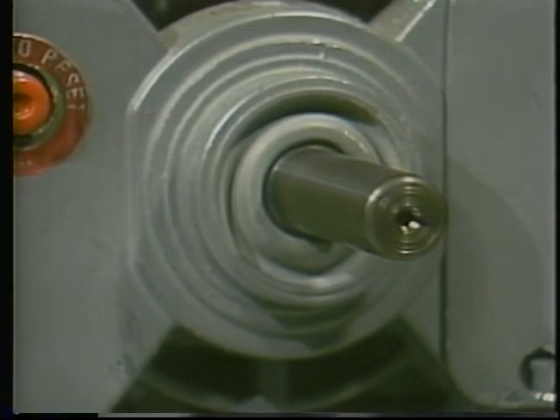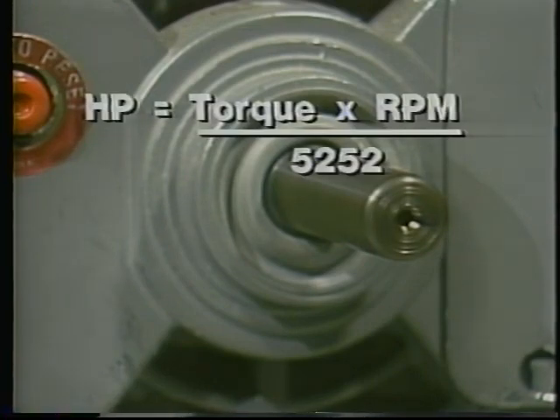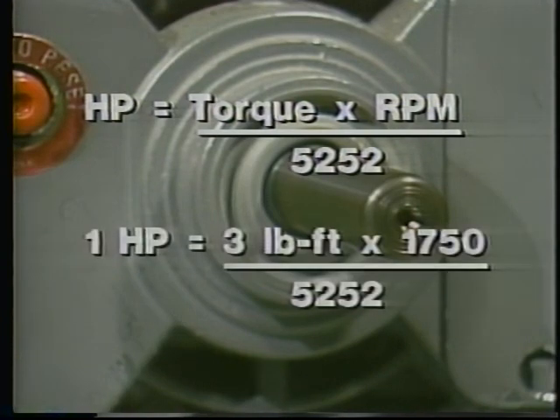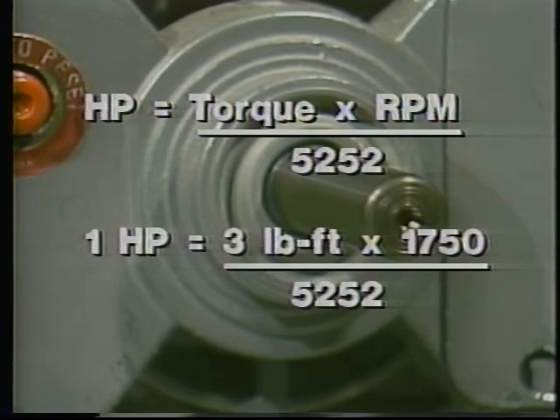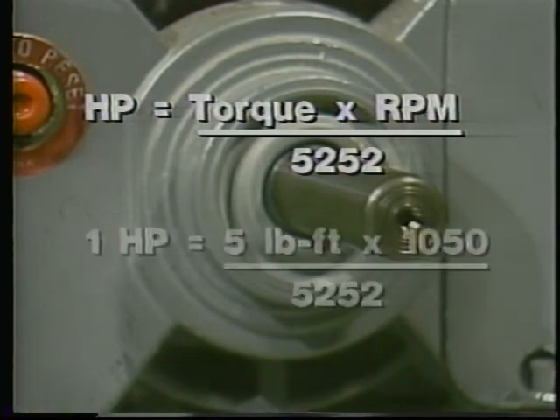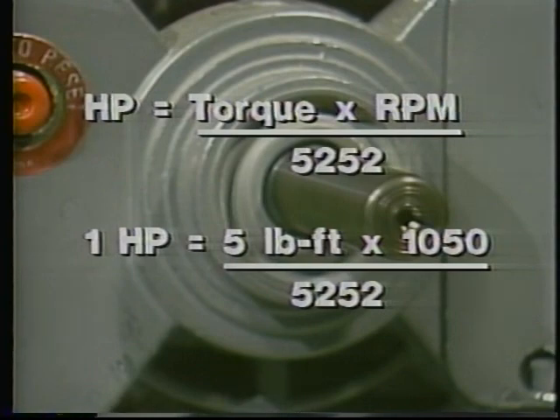This simple formula relates torque in pound-feet and motor speed in revolutions per minute to horsepower. If a motor is turning at 1,750 RPM, for example, it must exert three pound-feet of torque to produce one horsepower. It will also produce one horsepower if it exerts five pound-feet of torque and runs at 1,050 RPM.